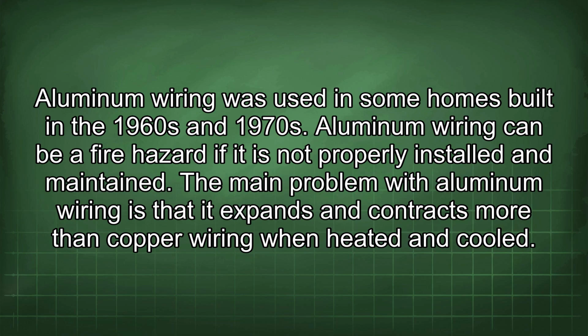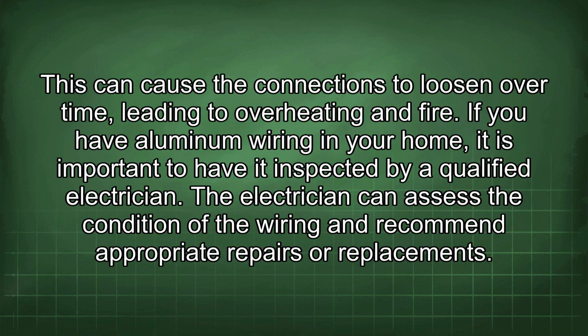Aluminum wiring was used in some homes built in the 1960s and 1970s. Aluminum wiring can be a fire hazard if it is not properly installed and maintained. The main problem with aluminum wiring is that it expands and contracts more than copper wiring when heated and cooled. This can cause the connections to loosen over time, leading to overheating and fire.